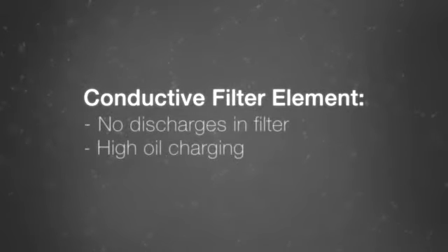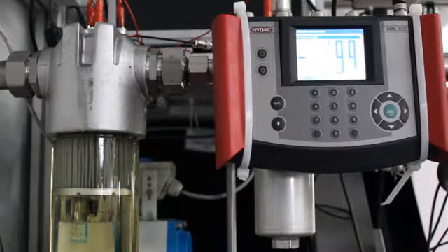Let's compare the charging behavior of three standard filters. First, the filter design that is most common, the conductive filter element. No discharge occurs at the filter element, but the filtered oil is highly charged. This means that uncontrolled discharge may occur in other parts of the system.